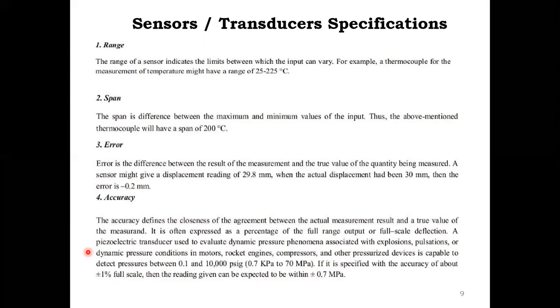Next one, span. The span is the difference between the maximum and the minimum value of the input. So the above mentioned thermocouple will have a span of 200, because the lower value is 25 and the higher value is 225. That is the maximum minus the minimum value. So the span of the thermocouple is 200 degrees Celsius. This is the span.